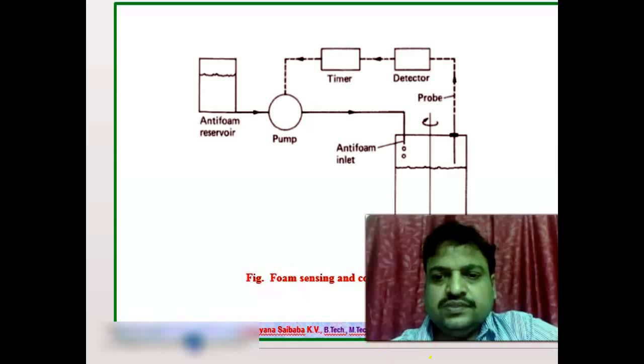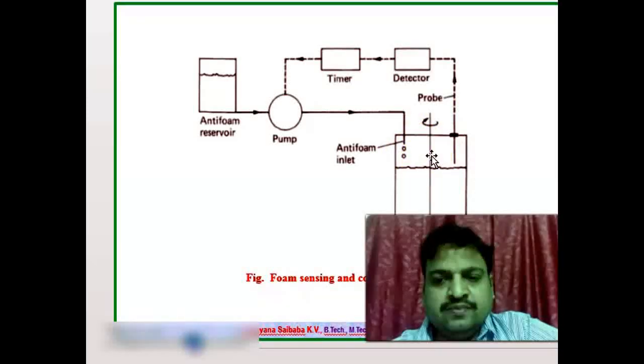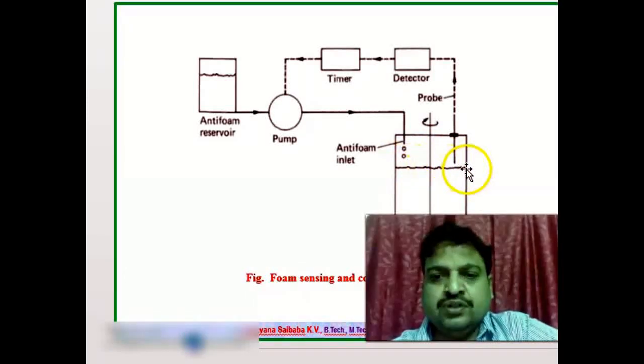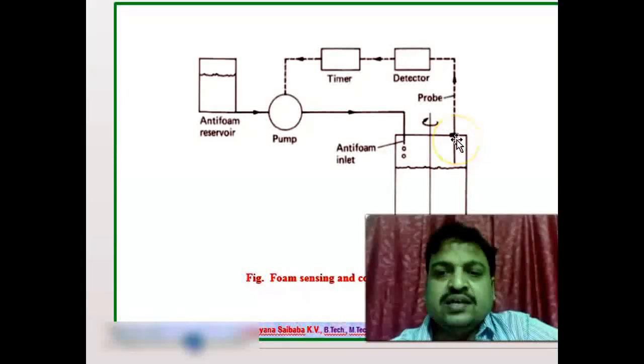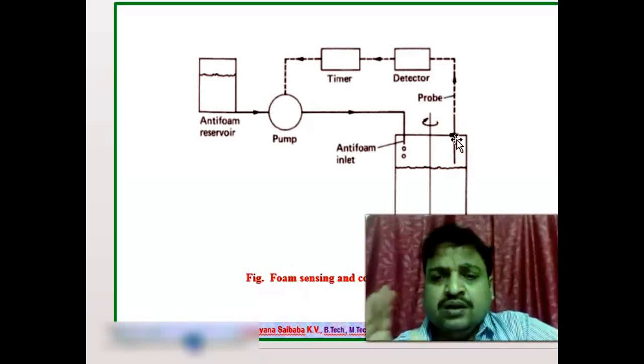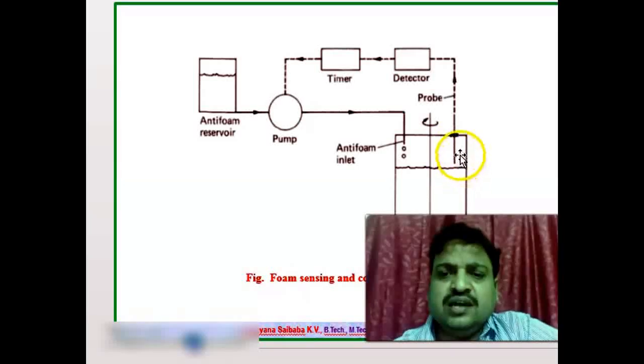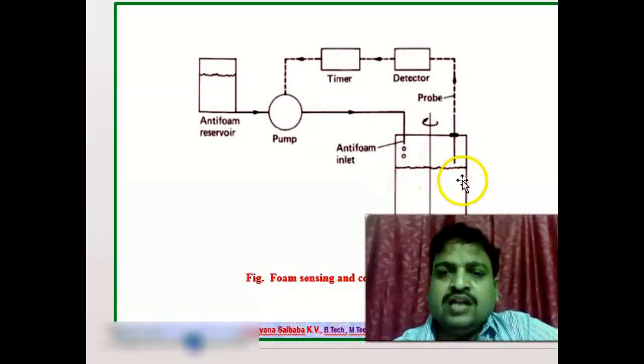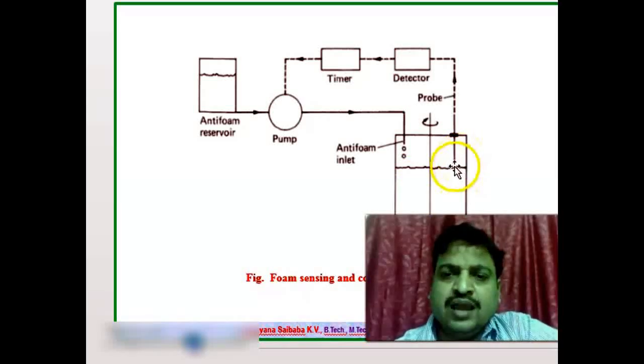Now we will see how the process is controlled using chemical methods with an example. In a traditional fermenter where foam is forming, we place a foam sensor above the fermentation broth. The sensor is a stainless steel probe — insulated everywhere except at the tip — positioned at a level above the fermentation broth. As foam forms and rises due to its low density, it travels upward and eventually touches the probe.